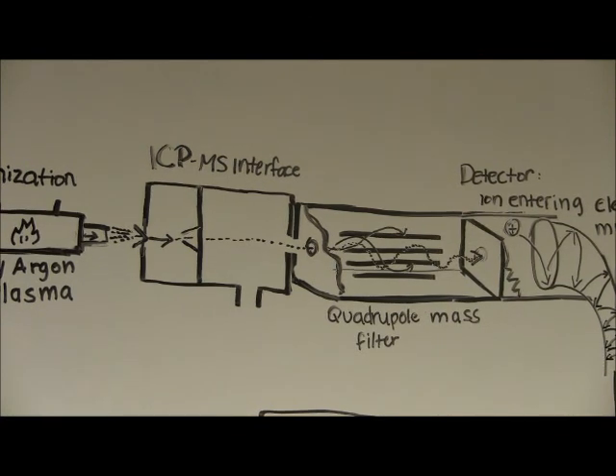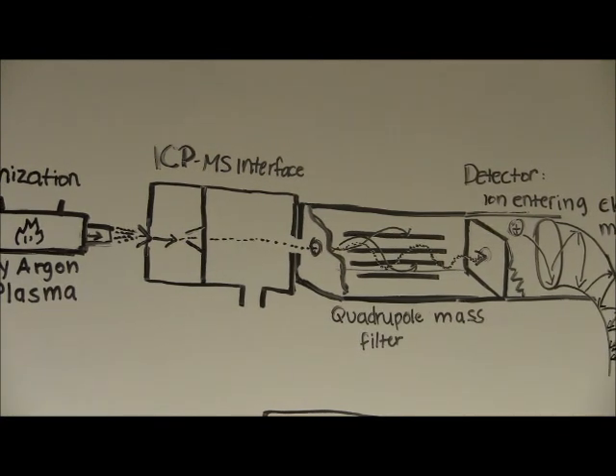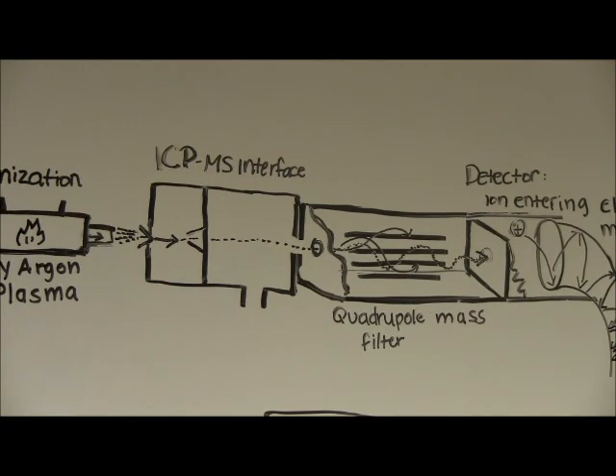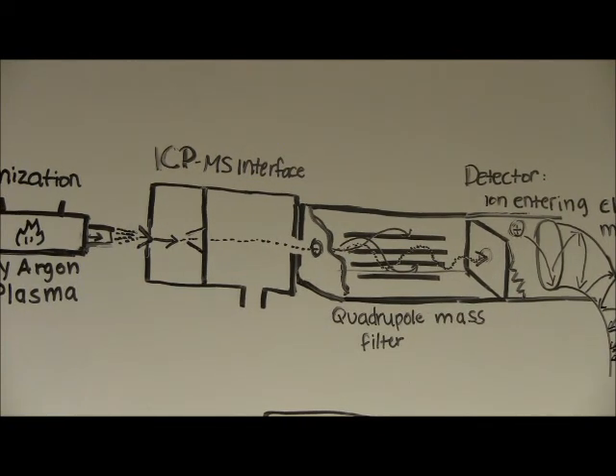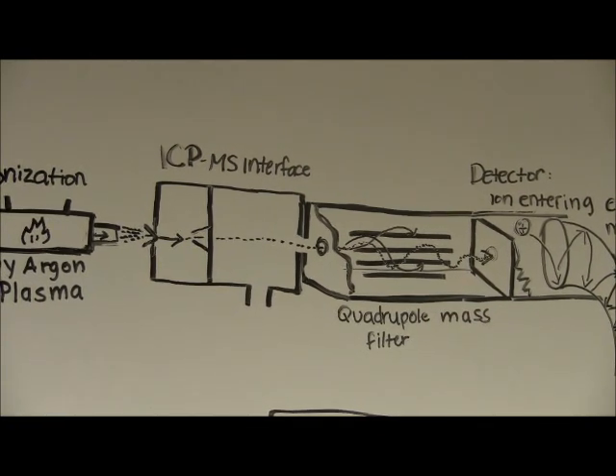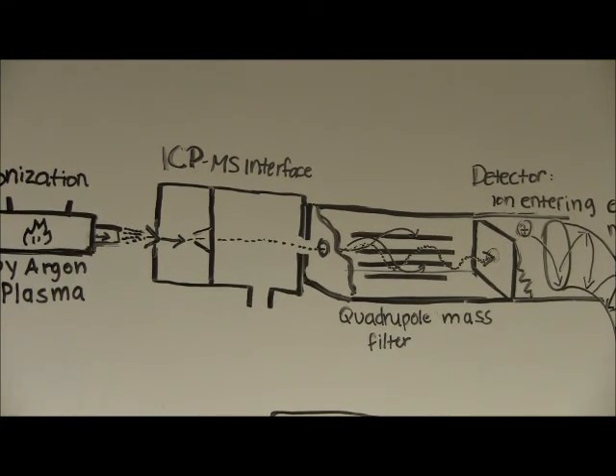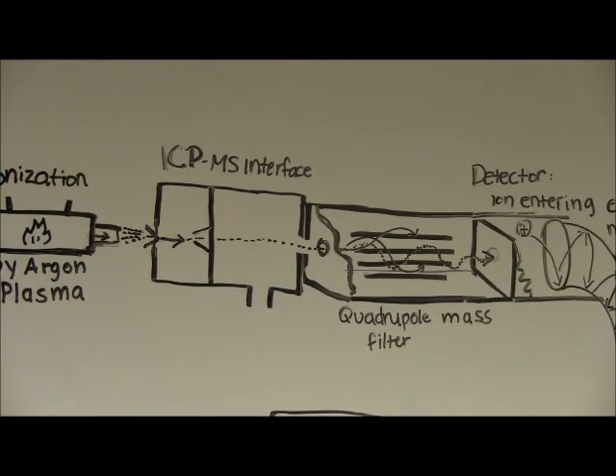In order to most efficiently reduce the pressure, several pumps are typically used to gradually decrease the pressure to 10 to the negative 5 millibar before the ion stream reaches the quadrupole. If only one pump were used, its size would be excessive to reduce the pressure immediately upon entering the mass spectrometer.